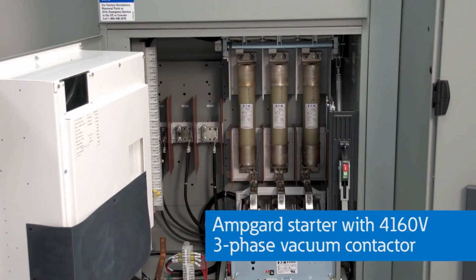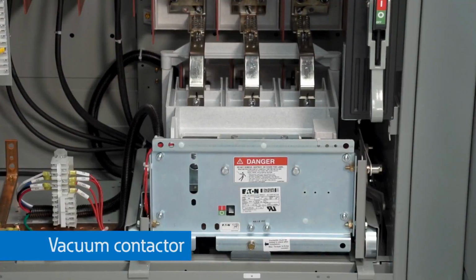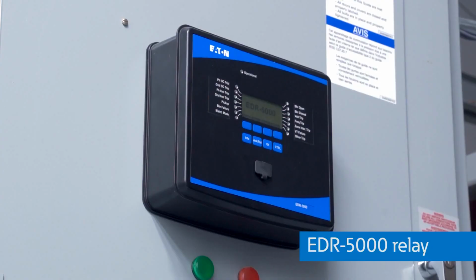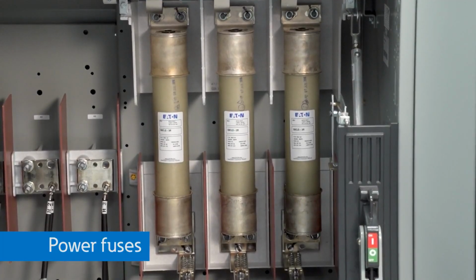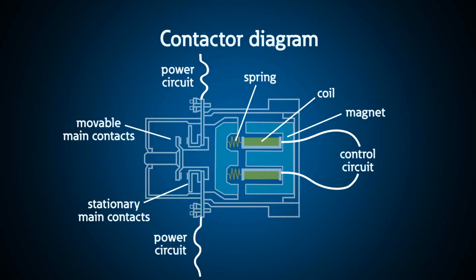This AmpGard medium voltage motor starter uses a vacuum contactor in a relay for overload protection. These power fuses provide fault protection for this motor starter. Let's take a look at the components that make up a contactor. These would include the main contacts, auxiliary contacts, coils or electromagnets, and springs.